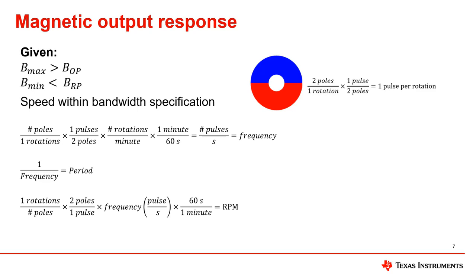The magnet shown here has two poles, which results in one pulse per rotation when using a single latch. If the magnet had four poles, that would result in two pulses per rotation. Using this information, the output frequency can be calculated by dividing the number of pulses per rotation by seconds. From there, RPM can be found using the output frequency previously calculated and the number of pulses per rotation.